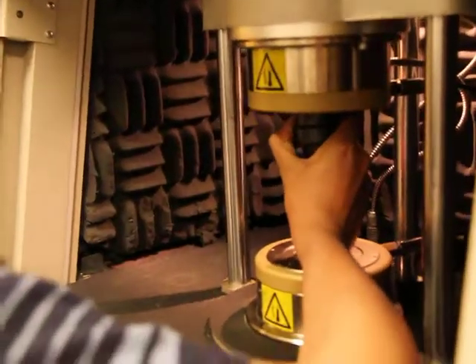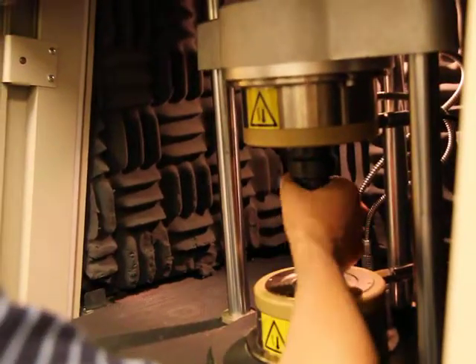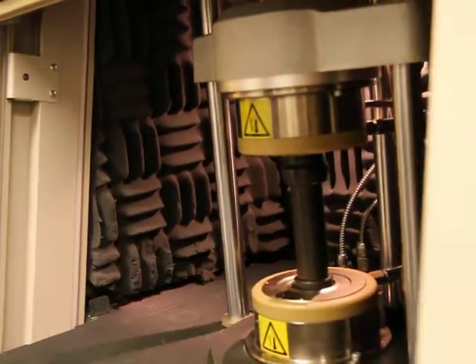You're not going to get the kind of shifts you do in DSC, but it's the same principle. You'd like to be starting from the same point. In the case of calibration in DSC, you have a floating baseline. From this, that baseline doesn't float nearly as much. So you think every test is good, or every week? No, when you start doing it every test, first of all, it takes a lot of time. Secondly, I'm not so sure you're not introducing more error than you're eliminating, because every time, even if it's a very minor change, it's going to be a minor change. I don't see any point in it, I guess.